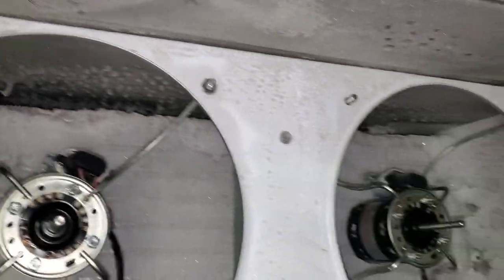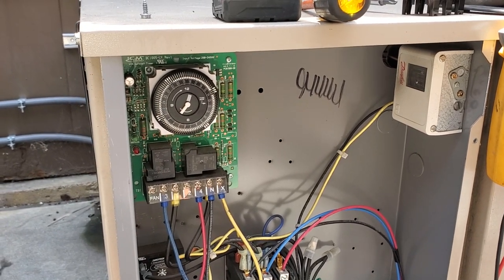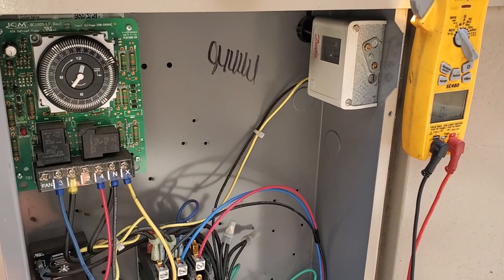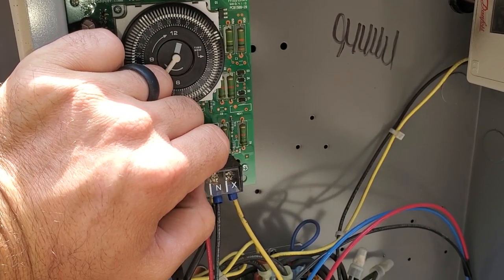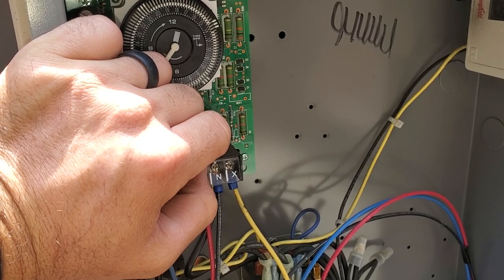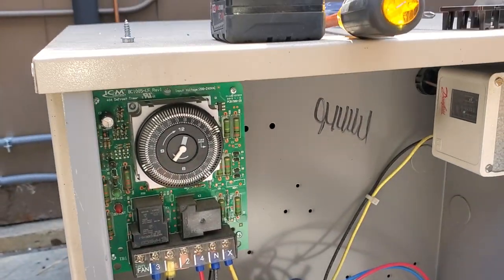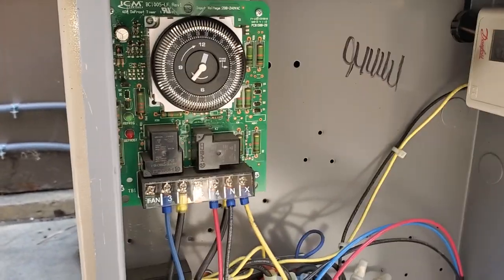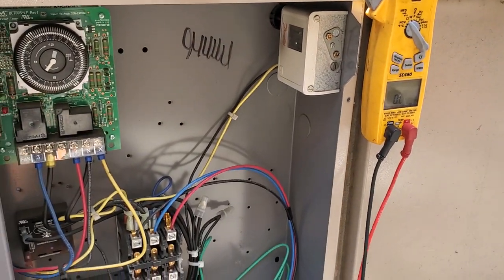At this point, I'm going to go ahead and throw it in a defrost and watch the unit defrost to see what happens. The door doesn't shut right, so that could be why it's iced up, but I still don't understand why the breaker was tripping. The unit is nowhere near just coming out of a defrost. It looks like it would have defrosted. It does three defrosts a day. I'm going to tone everything out to ground and see if we have any direct shorts in the defrost circuit.